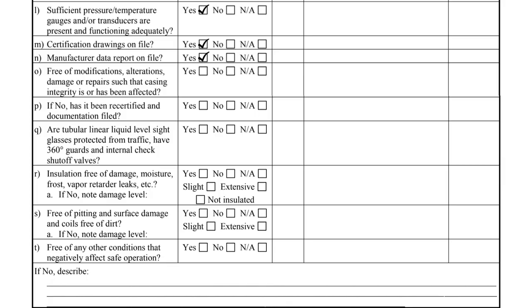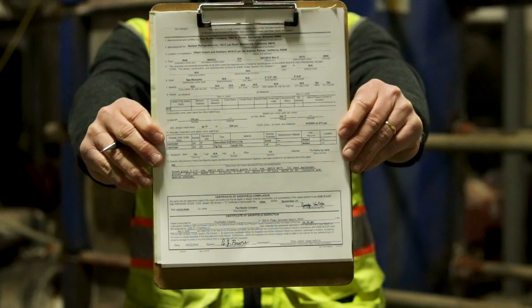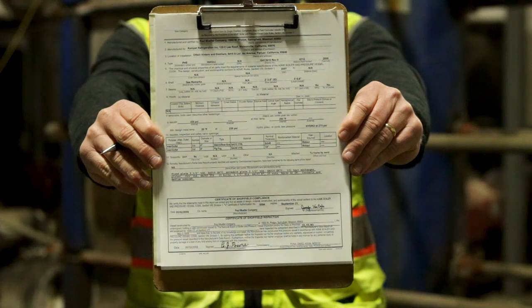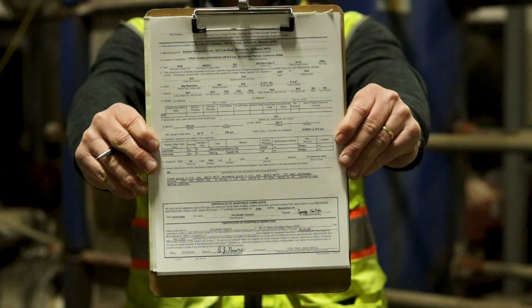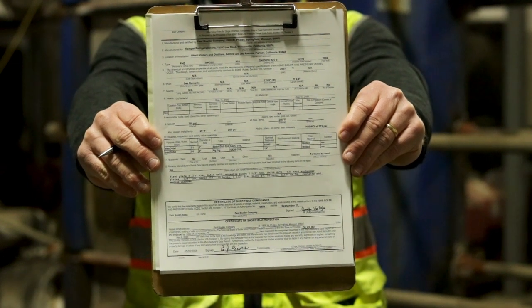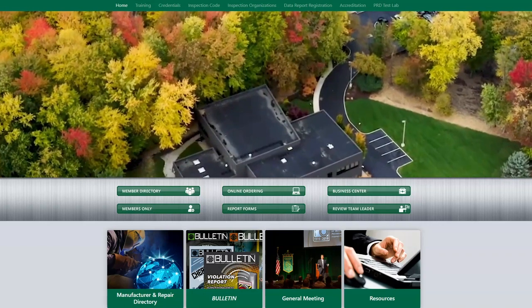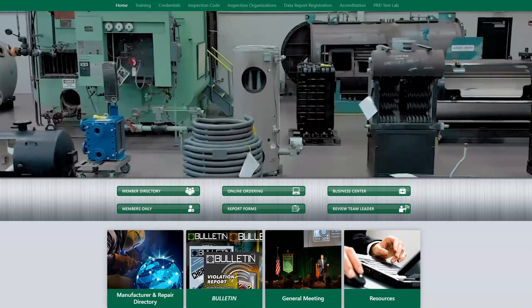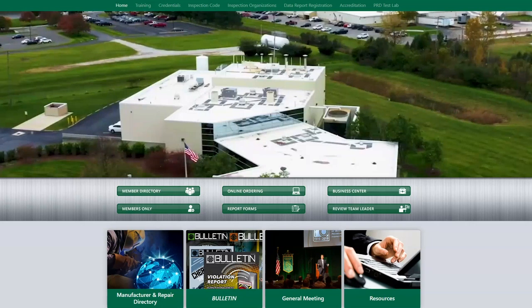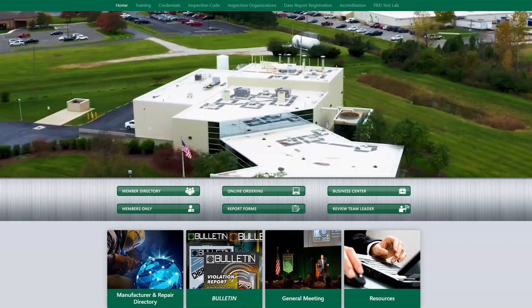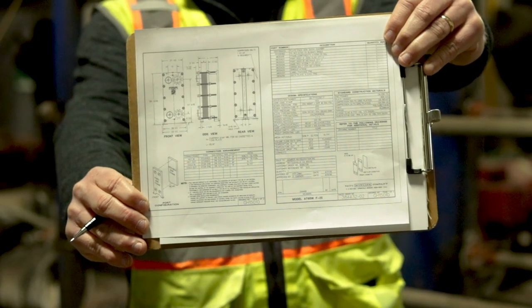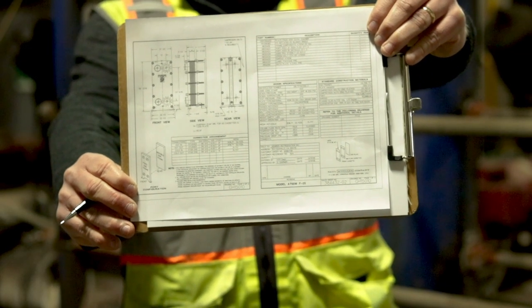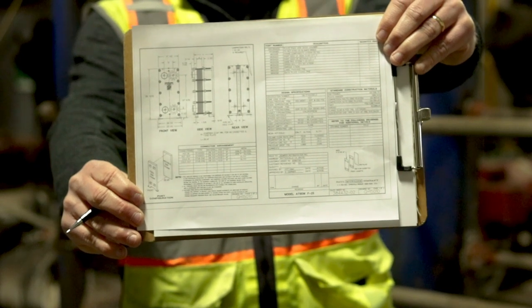Items M and N ask if the heat exchanger certification drawing and manufacturer data report are on file. The data report, commonly referred to as a U1 form, we like to call the heat exchanger's birth certificate as it documents the important characteristics of when it was manufactured. For heat exchangers registered with the National Board, the data report can be obtained from the National Board website for a small fee. The certification drawings are provided by the heat exchanger's manufacturer and should be available on site.